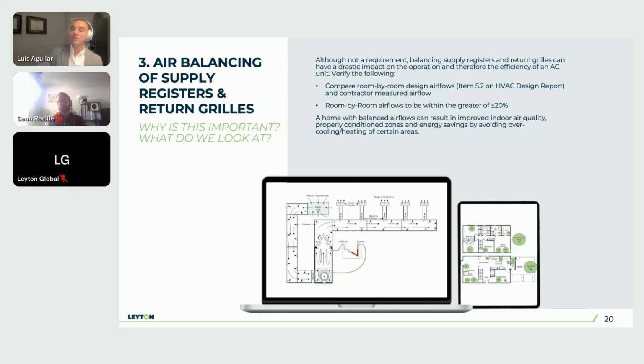And we will try to get within a ballpark range of those design airflows to ensure that every room is cool, right? What we don't want is a home where the control zone is usually the largest zone in the home. So let's say the big living room area is really cold, and then all the rooms are really hot. Because then what ends up happening is you could have humidity issues in the rooms because they're too hot, and overall the comfort is not there. So we want to avoid that. And so this is a very simple recommendation, and typically it's pretty simple to fix. What we can do is use dampers to manipulate the airflow throughout the unit, and try to get a little bit more airflow, maybe further down the ducts, to try to get within these design airflows for each zone.